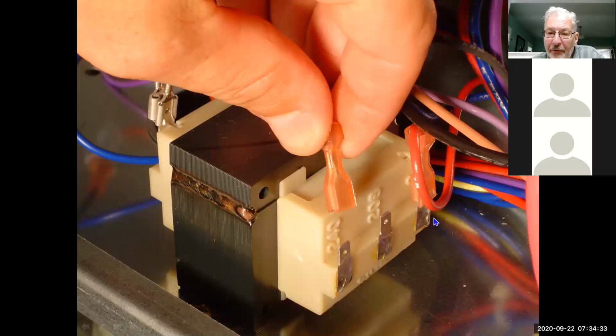One of the other things when you're doing startup or setup or even maintenance is make sure that the wire is on the proper tap. Again, the red wire goes on the common, and you move the blue wire from 240 to 208. If you move the red wire, it lets the smoke out of the control, okay? Always move the blue wire.